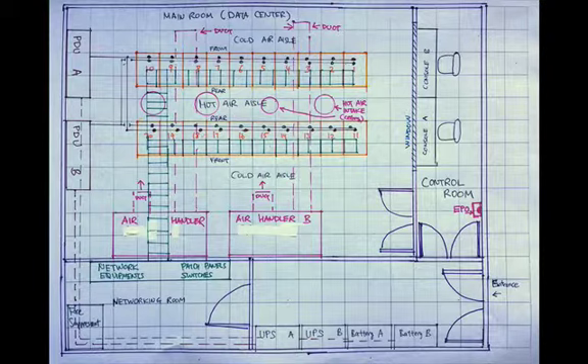This is the layout of the data center itself. Within the data center, there are 3 separate rooms. Immediately upon entering the data center through the main entrance, the UPS and its batteries will be accessible. There are 2 pairs of UPS and battery for redundancy. Further in, there is a networking room where all the networking wiring terminates. It houses all major network equipment such as the router, switches, and patch panels, as well as the fire suppression unit. This section should be less than 100 square feet.